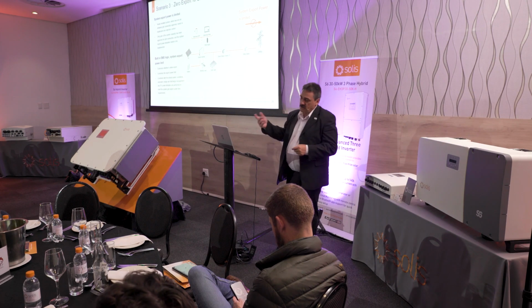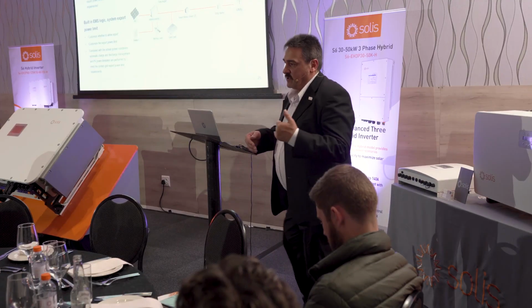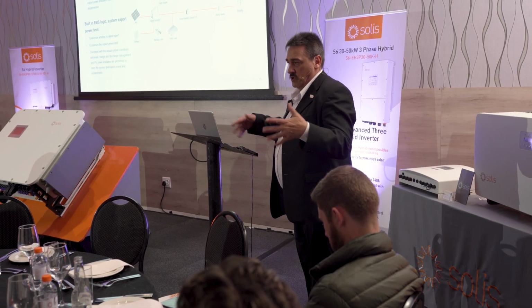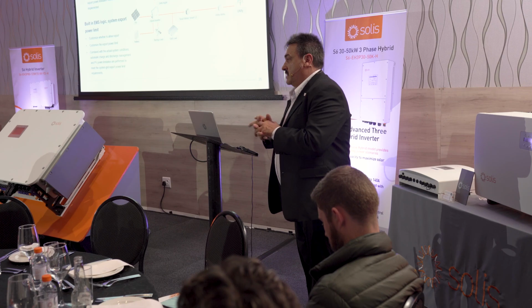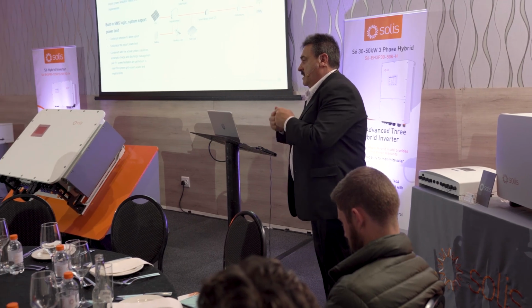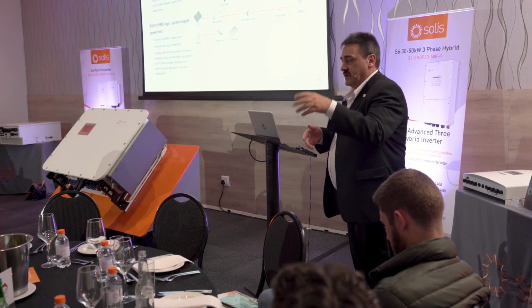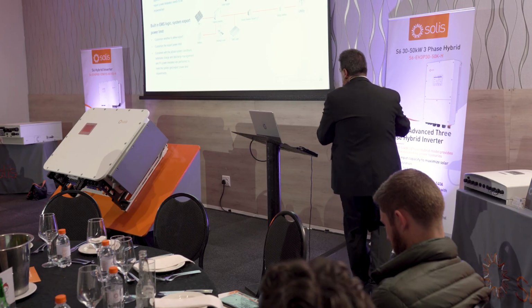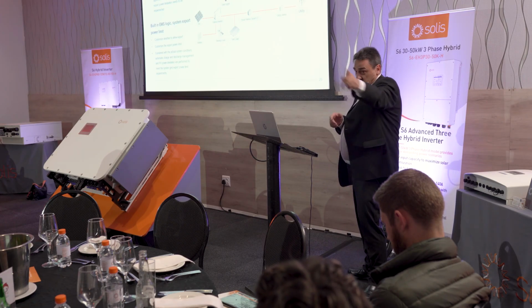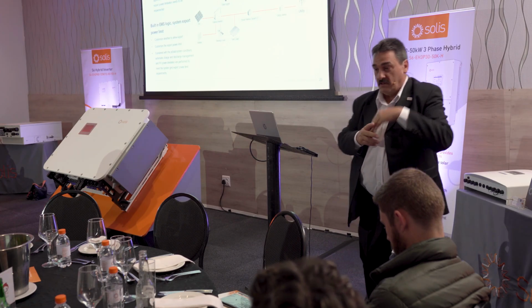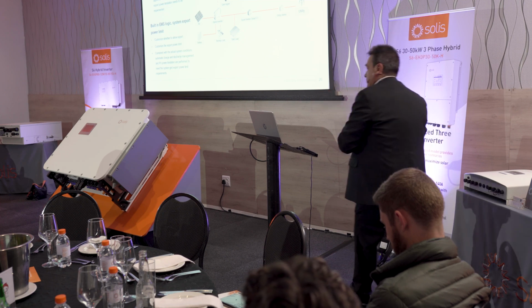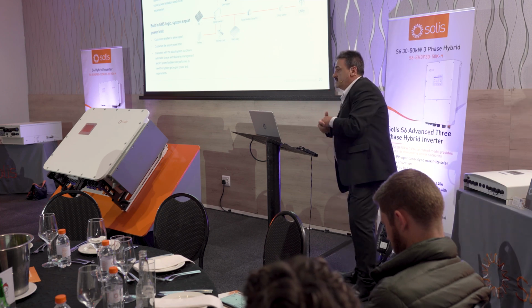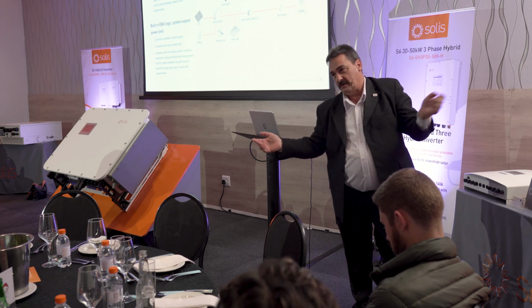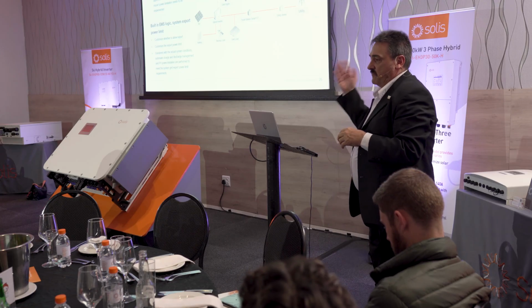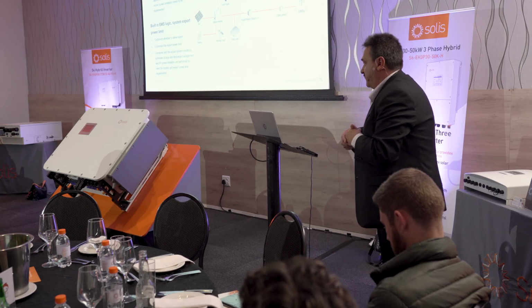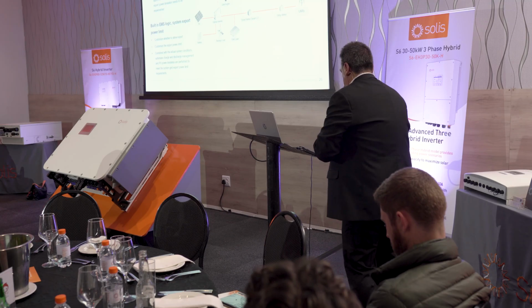Also, normally, especially on 3-phase systems, we have a problem of unbalanced loads a lot of the time. We get a lot of electricians going to the site and saying, add a plug, add a machine with a red phase. Can you add the fan or the air conditioner? Yep, red phase. Until that bus bar is full, and then it goes to the white phase, and then eventually there's nothing on a blue phase. We've all seen it, we all know it, and that causes a lot of problems for inverter systems, especially 3-phase equipment like a 3-phase grid tie.